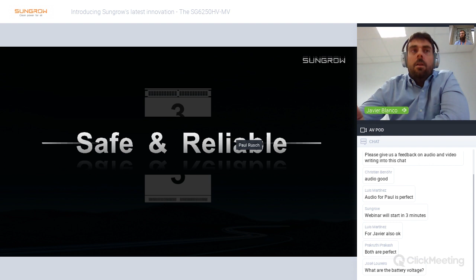An important point in all our Sungrow designs is the safety and reliability of the inverter, which is a crucial feature, especially in a central inverter or in any utility PV plant inverter. Reliability is a must, it's always considered very seriously in all Sungrow designs. One important factor that contributes to high reliability in this inverter is the IP65 ingress protection degree, which makes the inverter able to work in almost any environment. The corrosion rating can also be up to C5, so the inverter can be placed everywhere in the world without any risk of low performance due to environmental conditions.